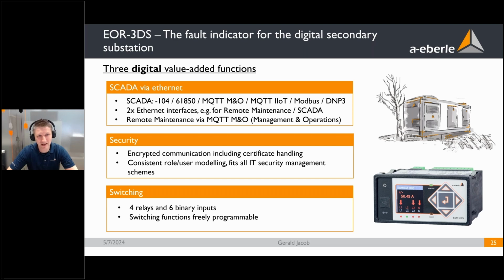So the first one, SCADA via Ethernet. We have a lot of standard protocols for SCADA communication. For example, the 104 protocol, 61850 GOOSE, Modbus TCP, DNP3 via Ethernet, and the 2 latest protocols we implemented are based on the protocol MQTT. There are 2: MQTT M&O, which means management and operations, and IIoT, which means Industrial Internet of Things. We will see in the 5th chapter why we split it into these 2 different protocols.